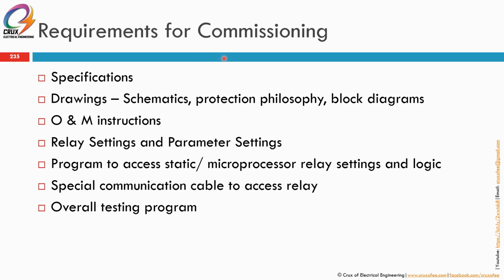So what is required for us to do commissioning? There are specifications, where the specifications of the equipment have been written out during the initial stage of the project, and the final drawings, which we normally refer to as the vendor drawings. The schematics, protection philosophy, block diagrams, and the operation and maintenance instructions, relay settings and parameter settings. This is very important. And then you also need a program to access static or microprocessor relay settings and logic.